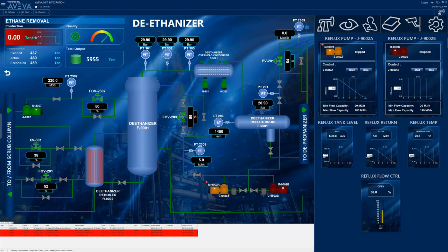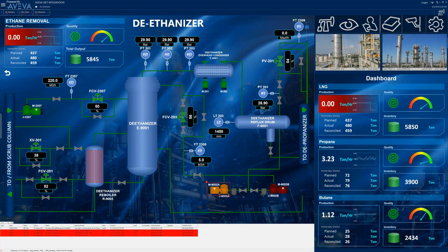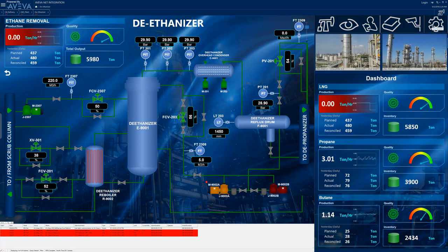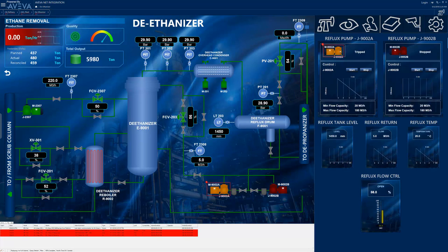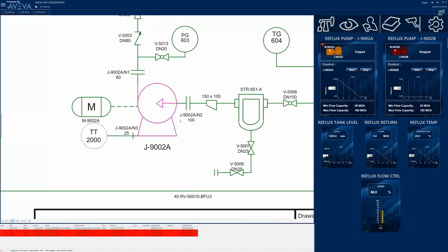Specifically, the faceplate shows that the pump's motor has tripped. Using the integration menu, the operator explores data from other applications, automatically presented in context of where their attention is right now. Clicking the CCTV icon displays the camera feeds for the current area. Selecting the AVEVA Net 2D icon brings in an interactive display of the actual P&ID from AVEVA Net's engineering database, automatically zoomed in to focus on the currently selected problem area, pump J9002A. The purple line color shows that it is the currently selected asset.